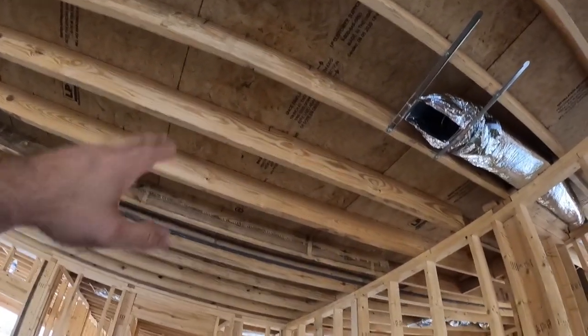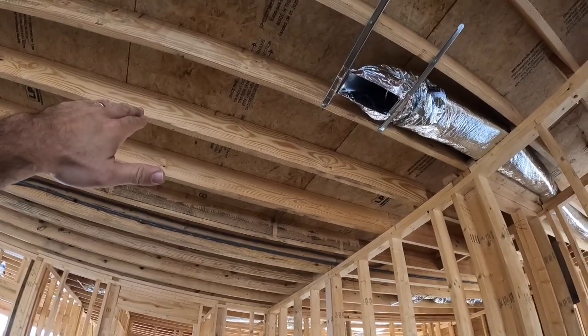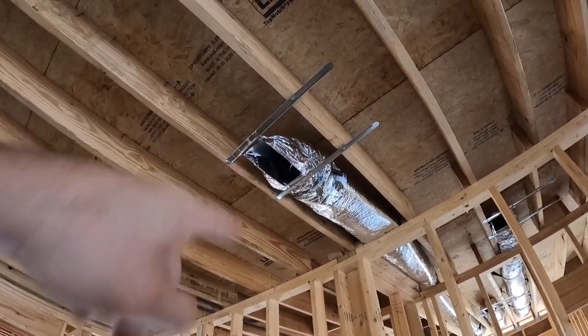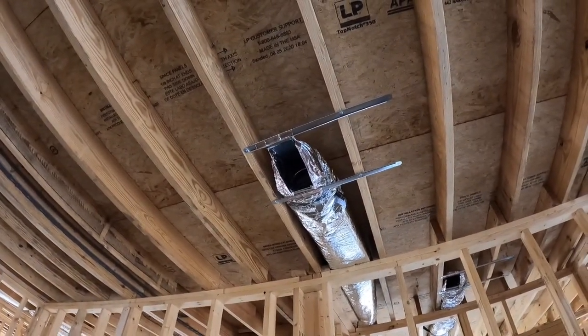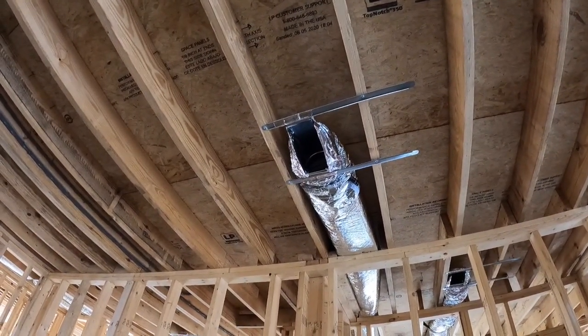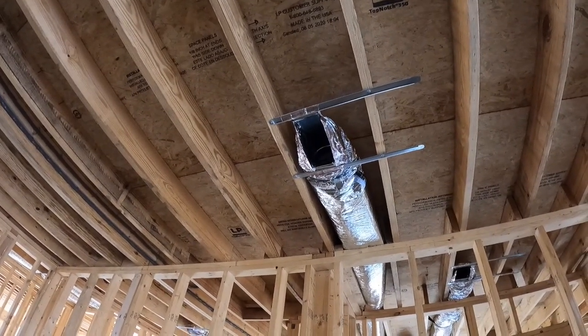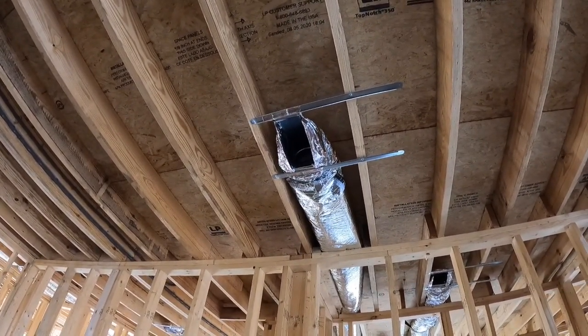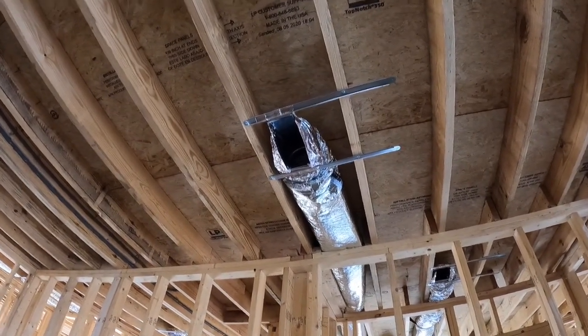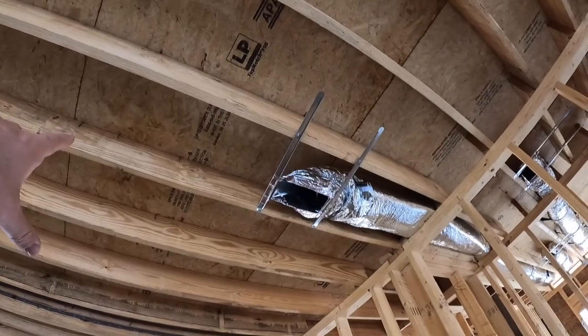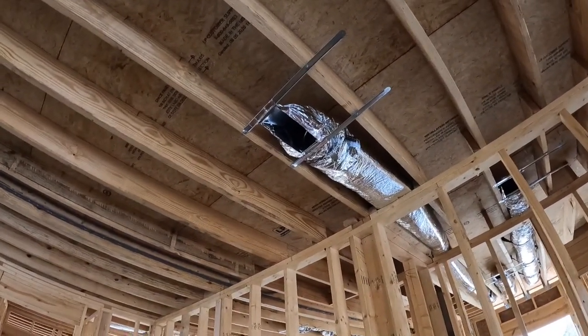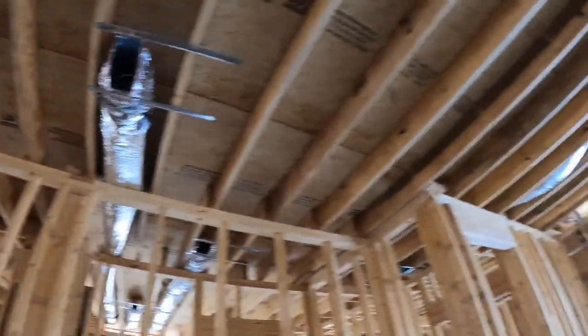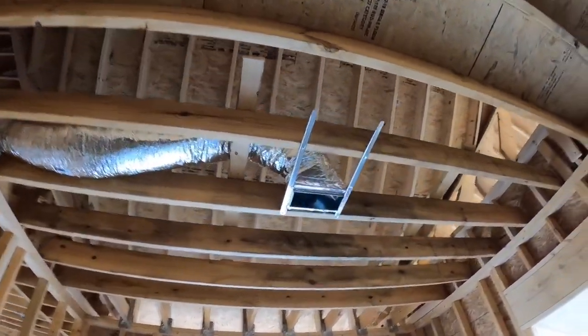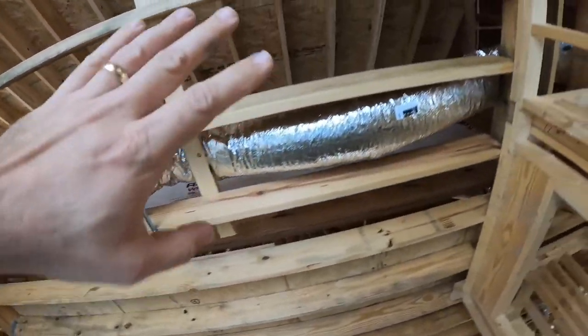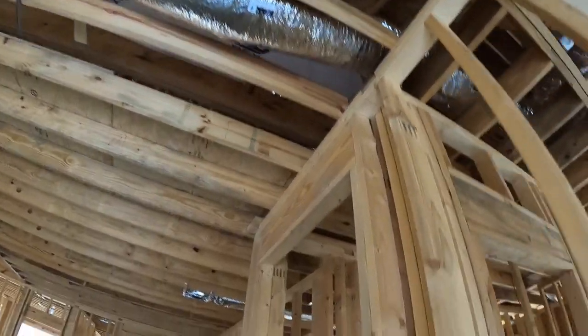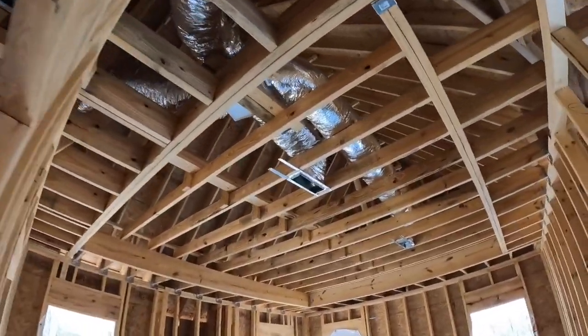So I think these are 2x8s, and we've got a 6-inch vent here, which has R8 insulation on it. So technically that should be a 10-inch diameter piece of flex, and I believe this is a 2x8 joist. So that gives you an idea of what we have to work with. But then when we get over here, we've got the breakfast area. This is open above here, so we don't have to worry about that. Same thing, master bedroom.